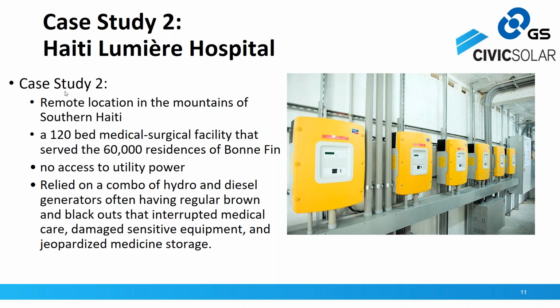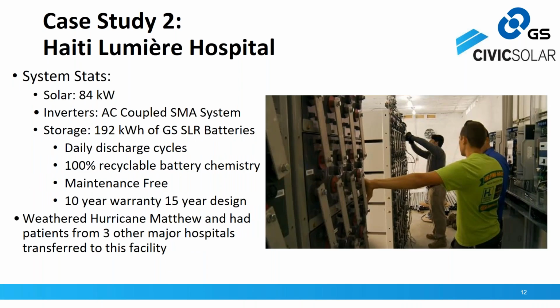We did this system as an SMA AC coupled system. We had 84 kW of solar on the roof, and 192 kilowatt hours of these high cycle life GS batteries, which we ran at 48 volts, using the Sunny Island multi-cluster control unit as the operations control for the site.